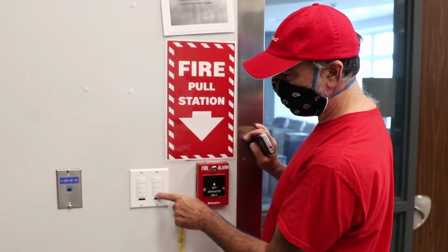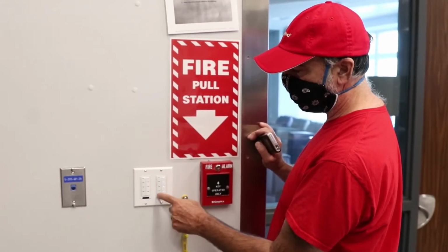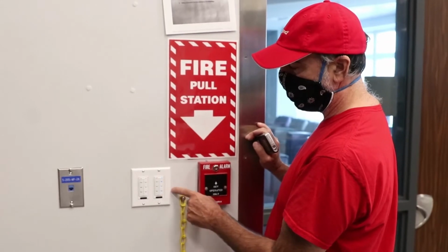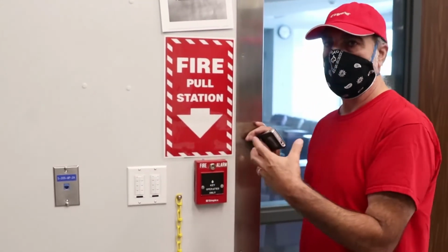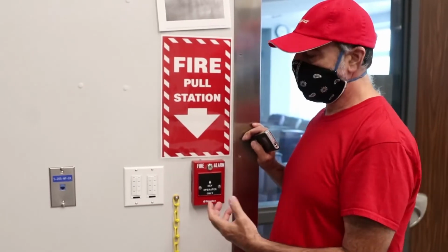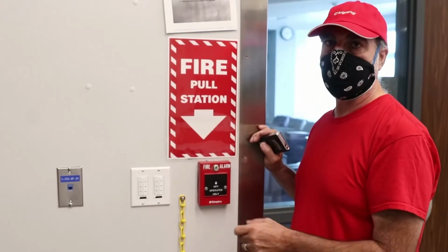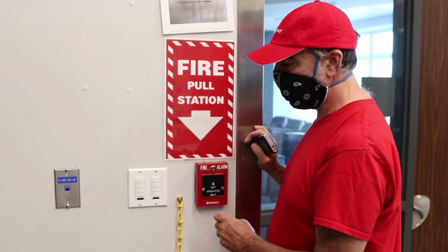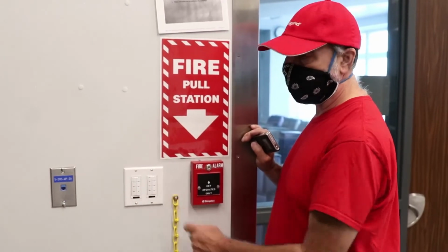And then this switch is flashing, and this is flashing, and these are all flashing because these are all spare switches. So when they flash, that means there's no light programmed into them, so nothing will happen and the light will just flash and eventually time out. So you're only using this set of lights and 3 of those.